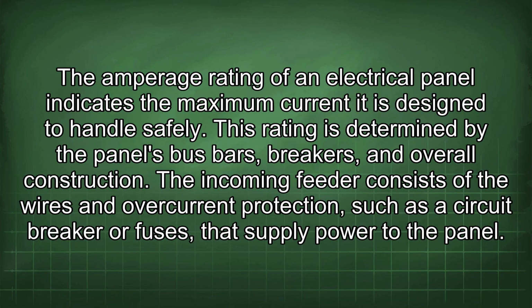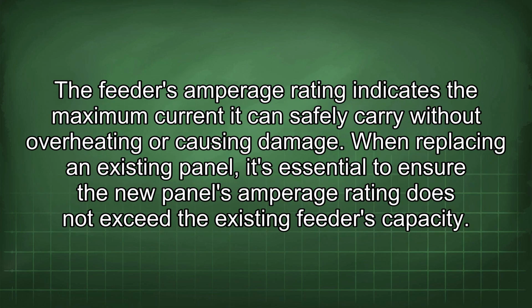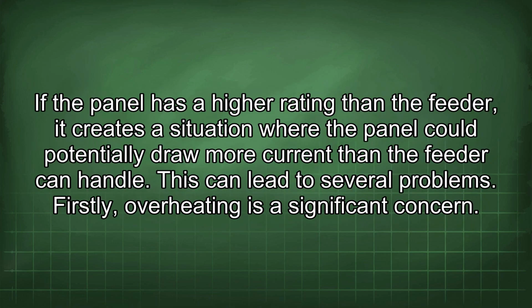The amperage rating of an electrical panel indicates the maximum current it is designed to handle safely. This rating is determined by the panel's busbars, breakers, and overall construction. The incoming feeder consists of the wires and overcurrent protection, such as the circuit breaker or fuses that supply power to the panel. The feeder's amperage rating indicates the maximum current it can safely carry without overheating or causing damage. When replacing an existing panel, it's essential to ensure the new panel's amperage rating does not exceed the existing feeder's capacity. If the panel has a higher rating than the feeder, it creates a situation where the panel could potentially draw more current than the feeder can handle.